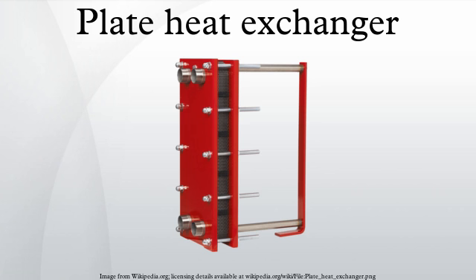Design of plate and frame heat exchangers. The plate heat exchanger is a specialized design well suited to transferring heat between medium and low pressure fluids. Welded, semi-welded and brazed heat exchangers are used for heat exchange between high pressure fluids or where a more compact product is required. In place of a pipe passing through a chamber, there are instead two alternating chambers, usually thin in depth, separated at their largest surface by a corrugated metal plate.